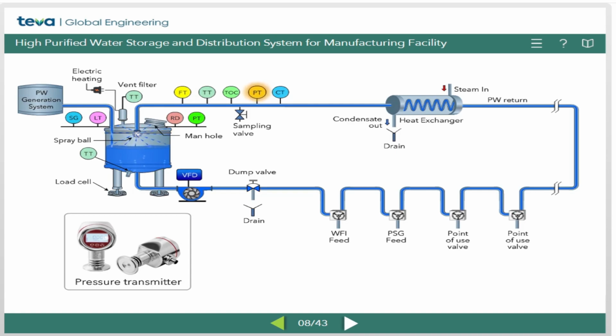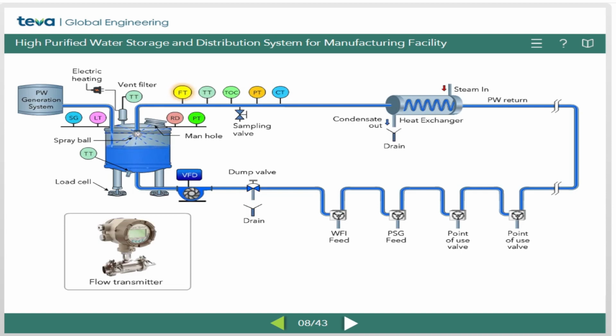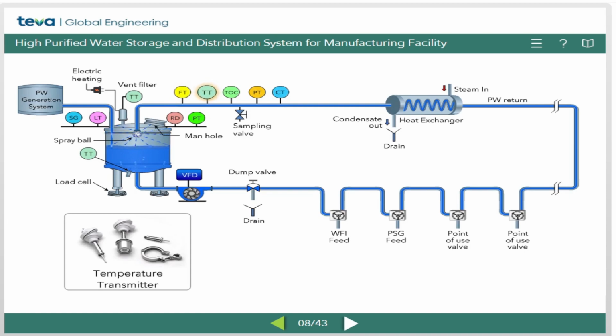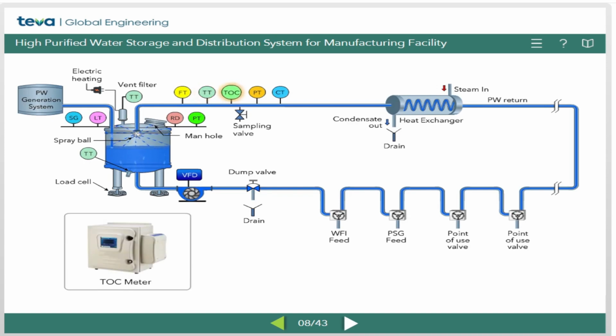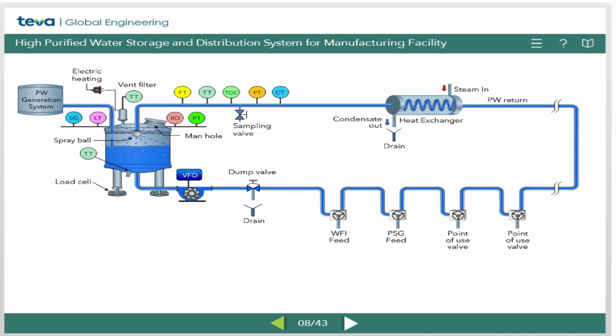Pressure transmitter to ensure the distribution loop to be always in positive pressure. Flow transmitter is used to control the return line velocity, ensuring turbulent flow in the pipeline to resist microbiological growth. Temperature transmitter to control the function of the return line heat exchanger responsible to maintain the overall system temperature within set limit as per sanitization SOP. TOC meter to analyze the total organic carbon in water. Inline sanitary design heat exchanger is used for sanitization of the loop, including the tank, as illustrated.